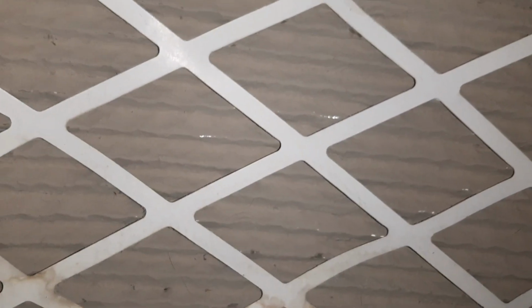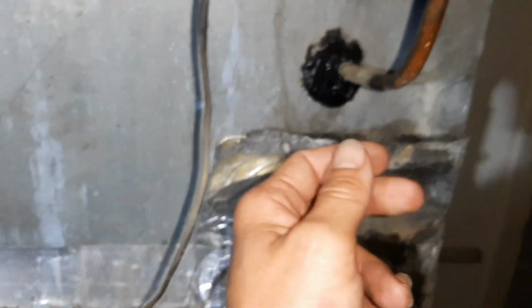Well, get that one, let's turn off that one. We're gonna probably pull the blowers just to clean the secondary heat exchangers, and we'll check outside. Didn't really find why the blower's running - shouldn't have had a call, but it's the least of my concerns at this point.